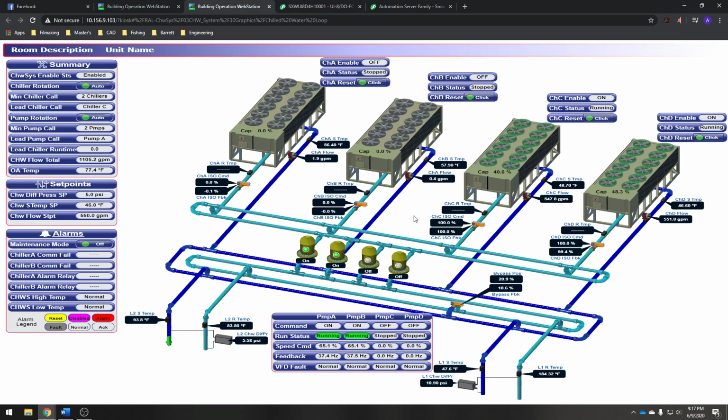So now that we've talked about how we control these things manually through the software, which is what we would call in hand, we'll talk about the overall system design. So the major point that we made was that we turned this system from a constant flow, you know, the pumps are on 100%, just running all the time on any chiller that's running. We converted a constant flow system to a variable primary system.